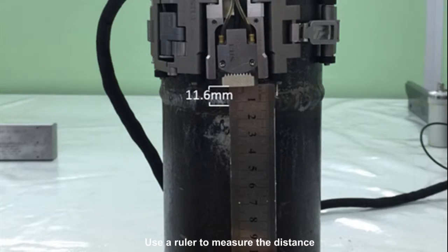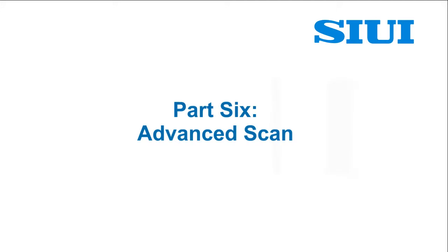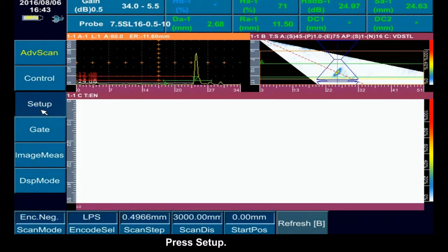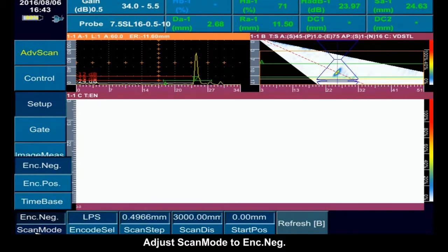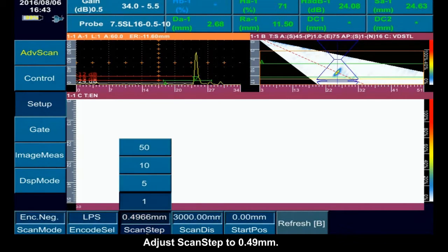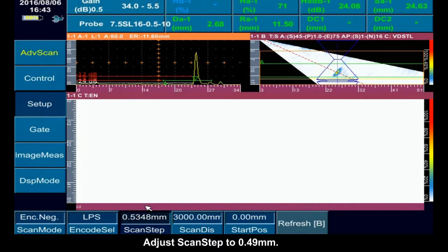Use a ruler to measure the distance between the probe flank and the weld center, ensuring it's consistent with the ER. Part 6. Advanced Scan. Press Advanced Scan. Press Setup. Adjust scan mode to encoder negative. Scan step to 0.49 mm.